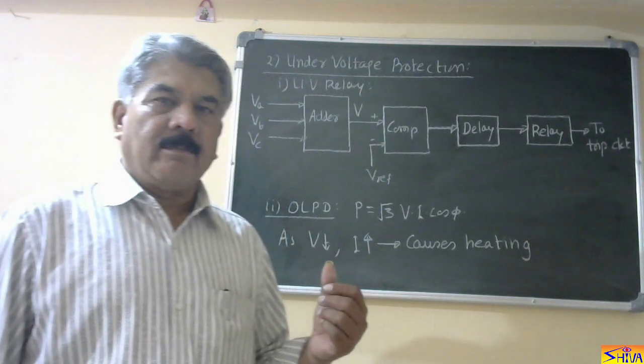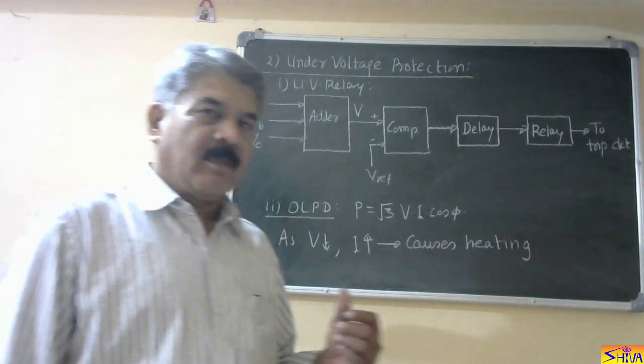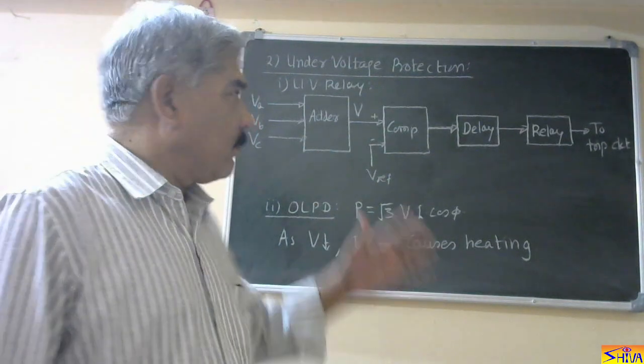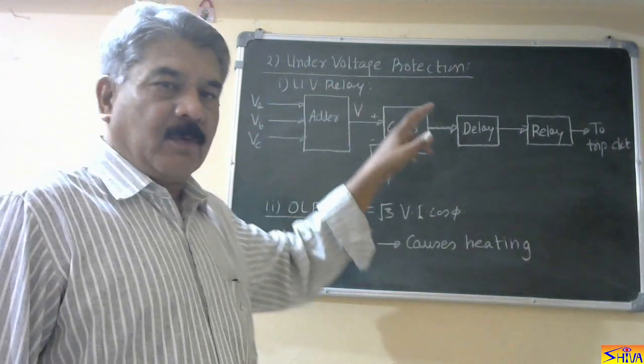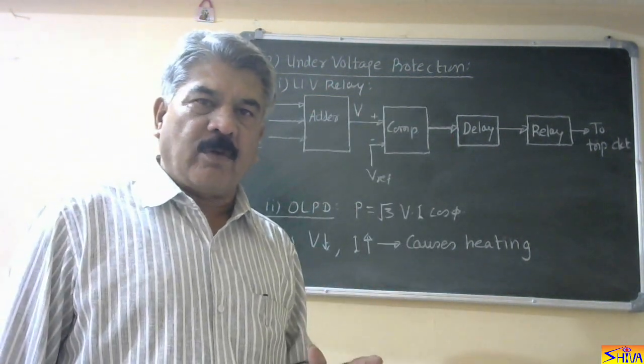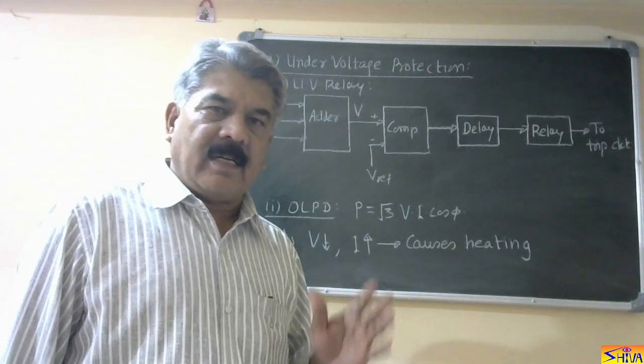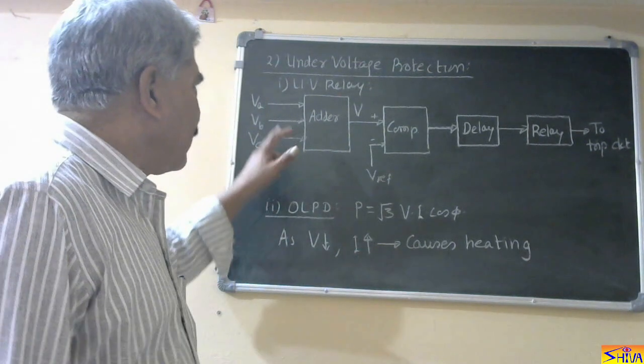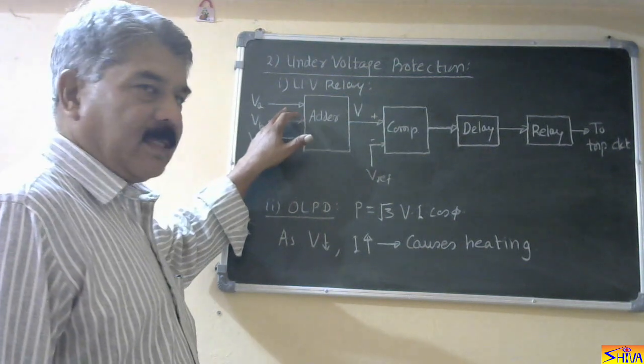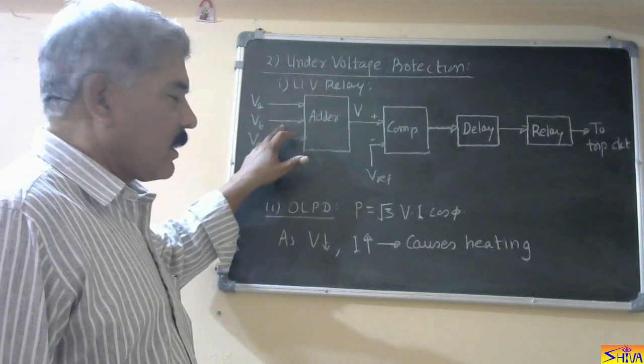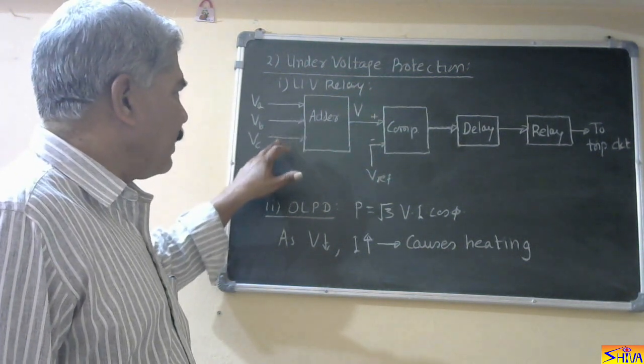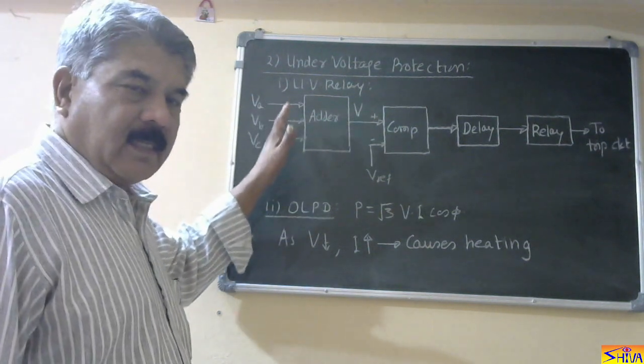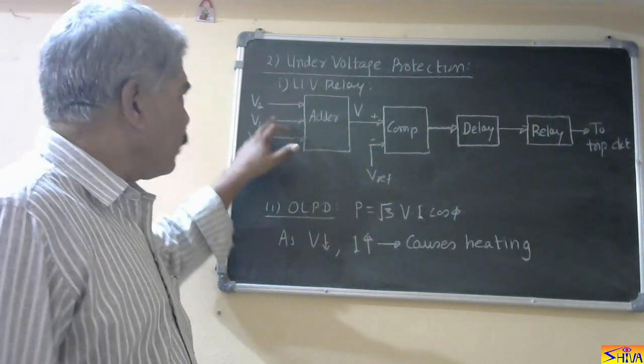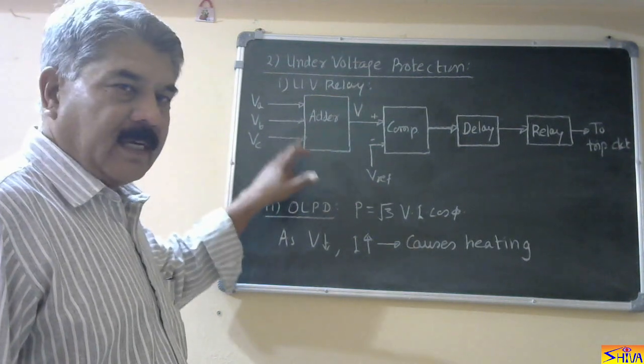Second is protection against under voltage. Now there are two methods. One, we install an under voltage relay, and that is used for large and very large induction motors. So here we take the voltage samples from the secondary of the potential transformer, VA, VB and VC. These samples are rectified, so here VA, VB and VC are DC voltages.